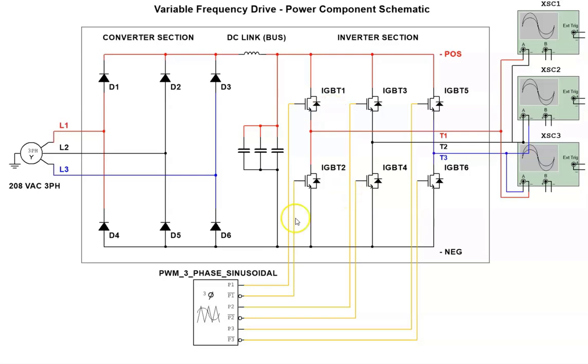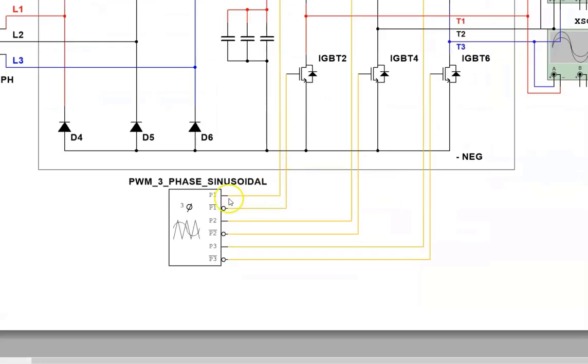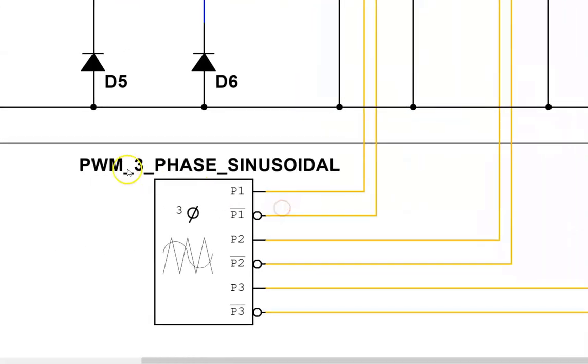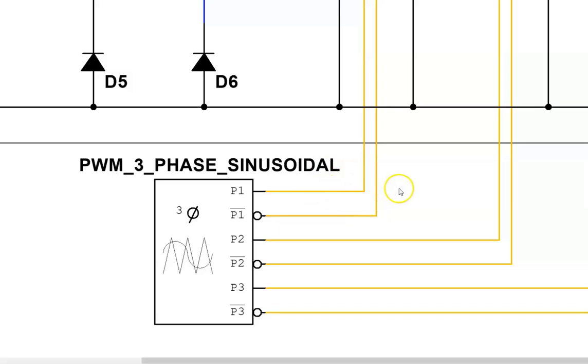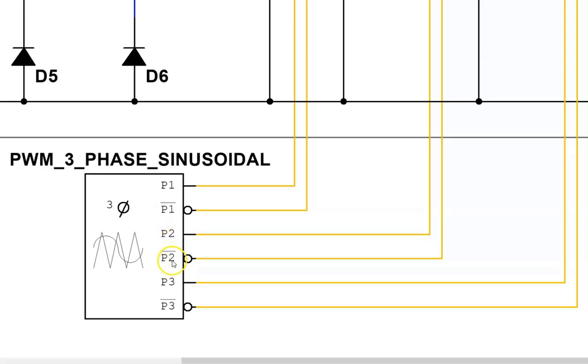And that is controlled by this driver circuit right here. It's called a pulse width modulation three phase sinusoidal driver. It tries to replicate the AC output at the inverter leads that connect to the motor. These two leads toggle - P1 and not P1 are always switching back and forth in a pre-timed sequence. The same for P2 and not P2 and P3 and not P3. So we can call it phase 1 control, phase 2 control and phase 3 control.